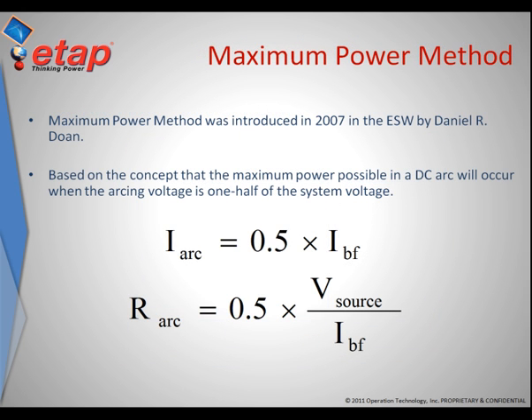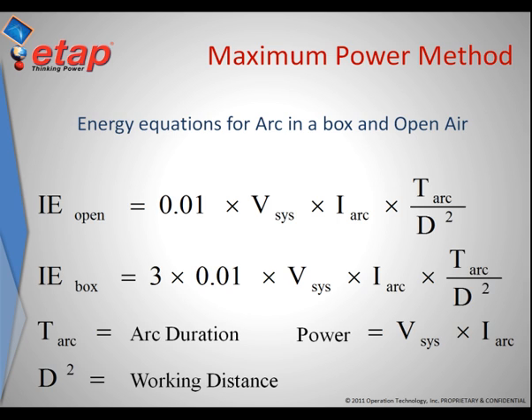The maximum power method is based on the fundamental concept that the maximum power delivered by the DC arc will occur at the point where the impedance of the system matches the resistance of the arc. This can also be defined as the point where the arcing current is half of the short circuit current, or the arc resistance is half of the source voltage divided by the DC short circuit current. Using the voltage drop calculations, one can determine these relationships.